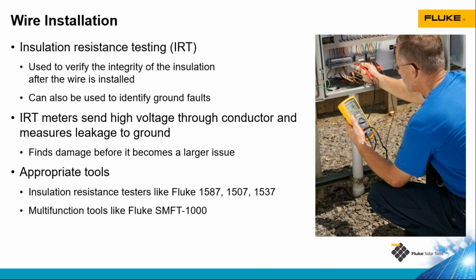It is the solar multifunction tool. It's designed to do all the tests required by the IEC standard, including insulation resistance testing. And it can do a standard test that we would use any of the other tools to do, which would be testing between the positive conductor and ground or the negative conductor and ground in our circuit of solar modules. We'll also do a different insulation resistance test, which is unique to this tool. It will take the positive and negative of our string of modules, short circuit them together, and then test that short circuit to ground. And by short circuiting that string of modules, we eliminate any voltage potential between the positive and negative and ground. So we get a bit more accurate test and a safer test. And it does that short circuit within the tool, and then it will break the short circuit when the test is done. So it makes it very easy for the technician to conduct that test.